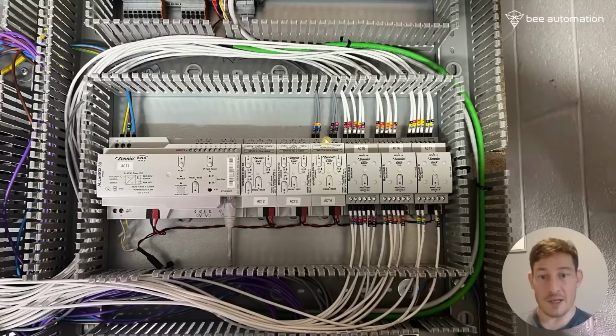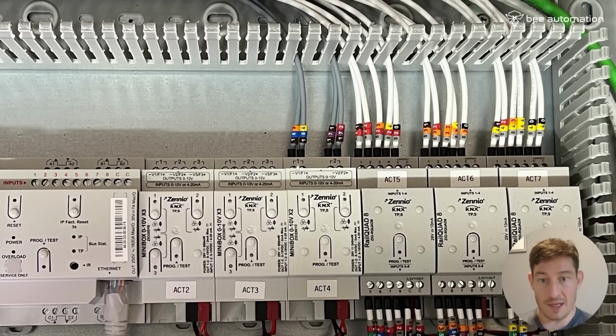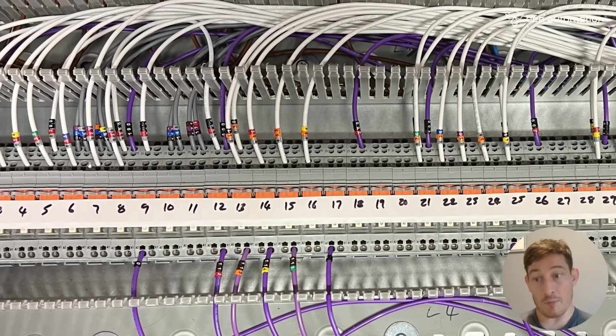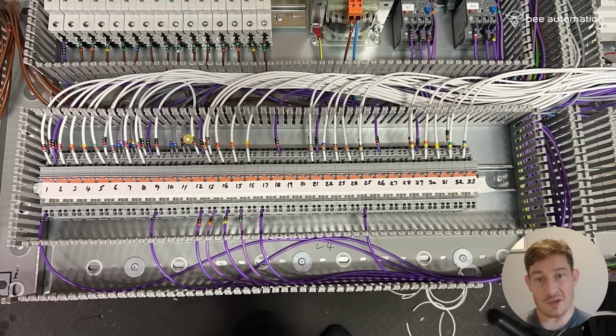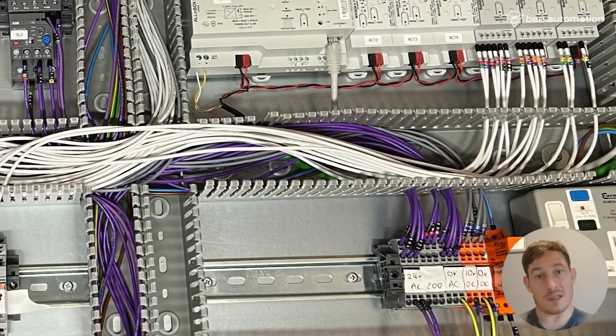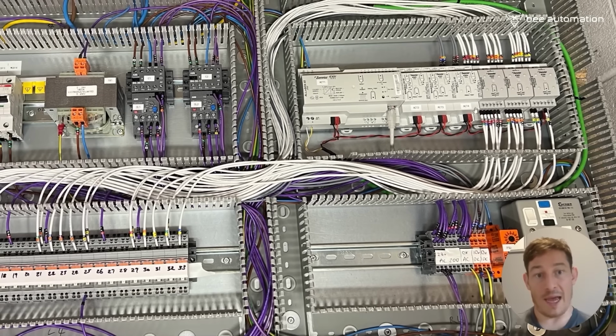So yeah, as you can see, the first cables were these 0 to 10 volt outputs for boiler 1 and boiler 2. They're going via some relays where you can see the greys here. We've also got some additional greys coming from the constant 10 volts, which is for when the cam switch is set in hand, so manual, and we're just using a constant voltage from this power supply to feed the boilers rather than having automatic control coming from the PLC.